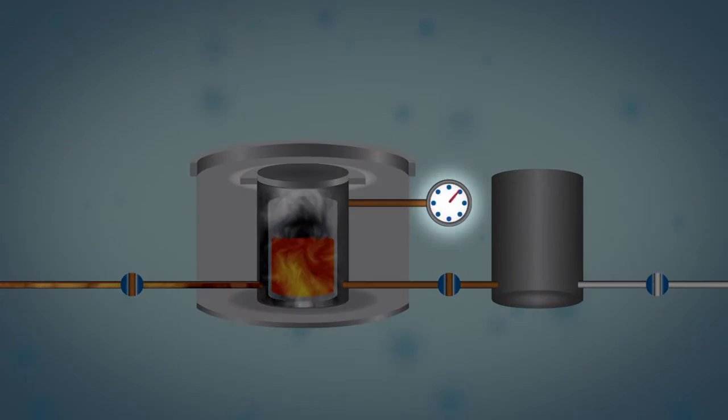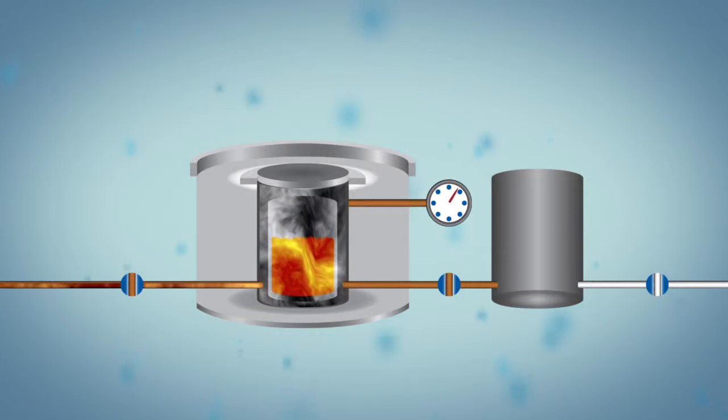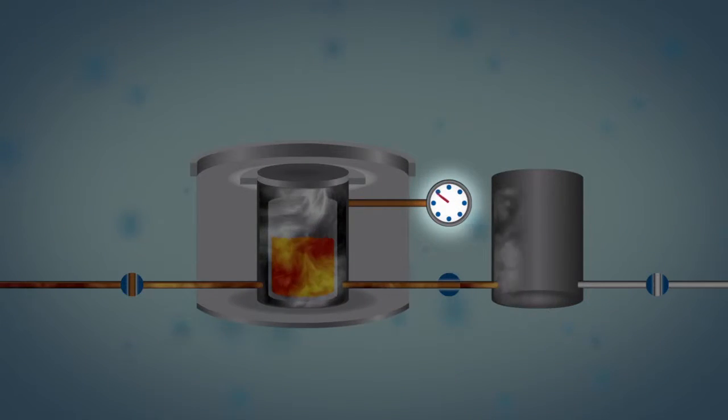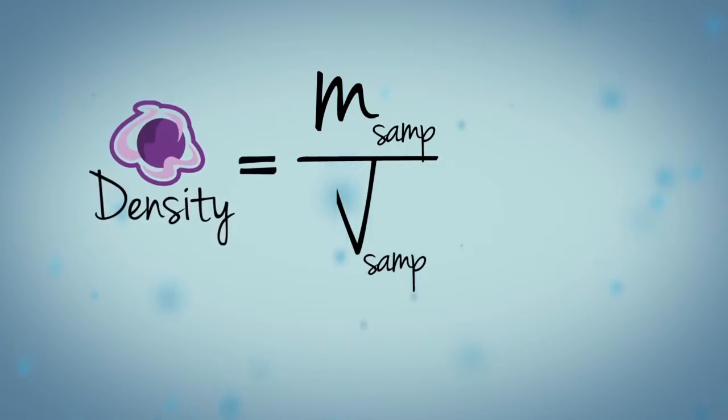Pressures observed upon filling the sample chamber and discharging the gas into a second empty expansion chamber produce a ribbon volume value. The AccuPyc divides this volume into the sample weight and automatically calculates the skeletal density.